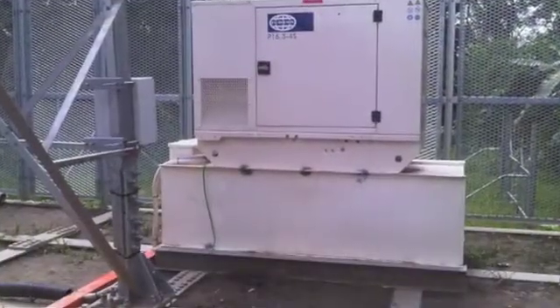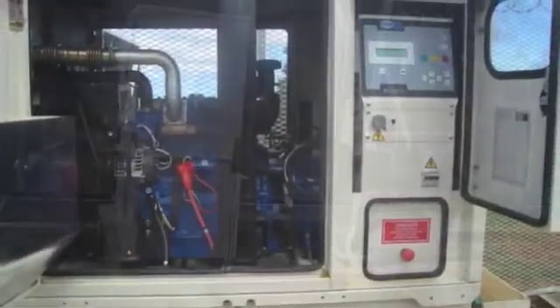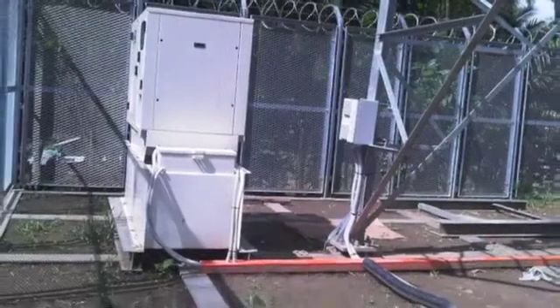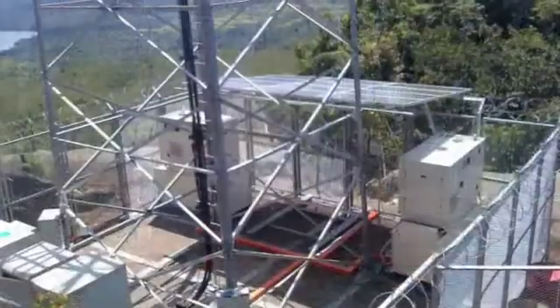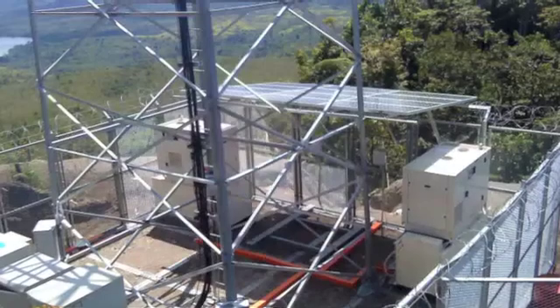Our systems have been retrofitted to existing sites powered by diesel generators running 24/7. It enables the generator to run for shorter periods at a higher load, typically 75 to 90% of their rated capacity. This gives an immediate 50% fuel saving and associated reductions in carbon dioxide, nitrous oxide and particulate pollution.